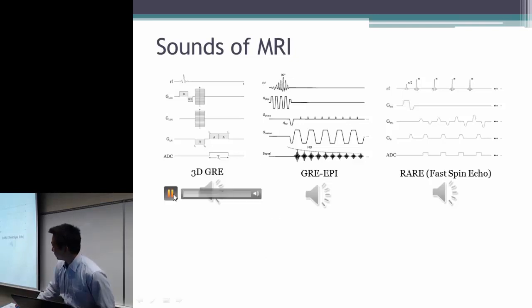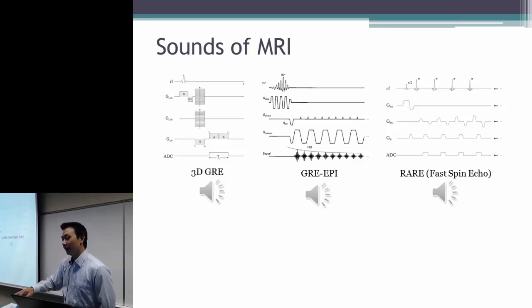So I'll just stop it. What is the sound in between? Sound in between what? Yeah, the continuation of the sound is like frequency encoding, right? Yeah, it seems that it goes up and down. Yes, those ups and downs are the phase encoding gradients. The steady sound is the readout gradient, and if you listen over a wider span of time, you can hear the up and down of the phase encoding gradients.